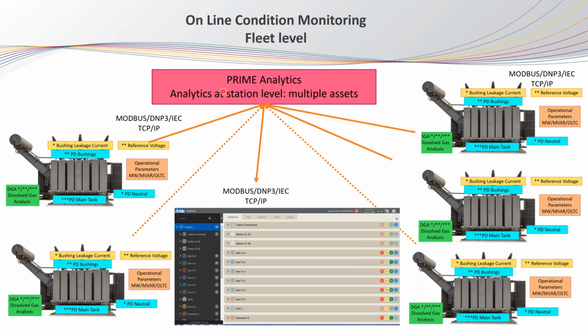So in the end, the most important thing, you are going to put, of course, sensors on each transformer or the transformers that are somehow critical in your asset. The most important point here is to have the possibility to access all the measured data remotely, and it can be done through a web interface system. So in this way, you'll be able to have an overview of the trending data of all your assets. You can have, for example, the measurement of the PD of the bushing from this transformer. You can compare it with the PD measurement of another bushing from another transformer and see if there are any abnormalities in the increasing trend, and so on.